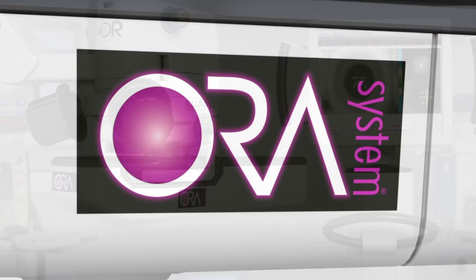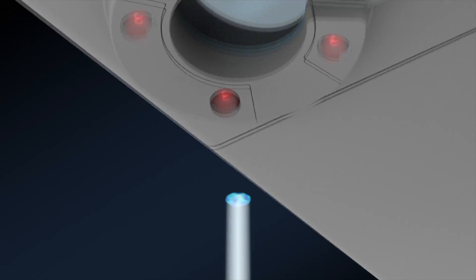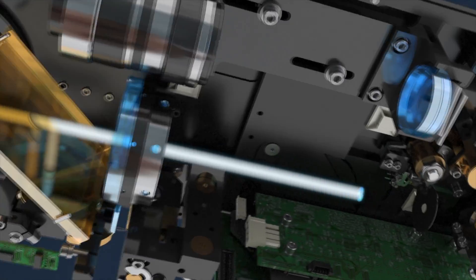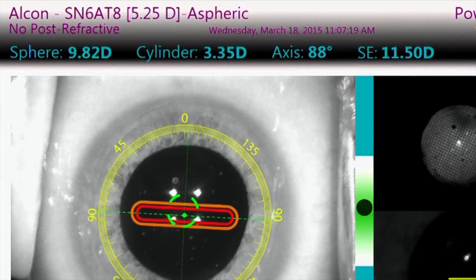Now with the ORA System, we're actually able to verify these lens measurements on the operating room table after the cataract is removed. The system takes about 40 optical measurements in just a few seconds while the patient fixates on a red light.